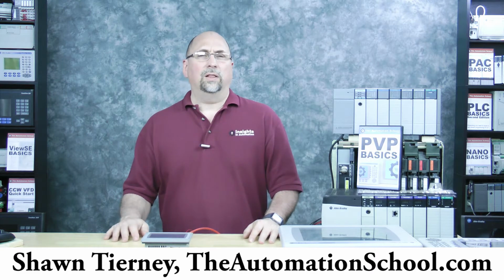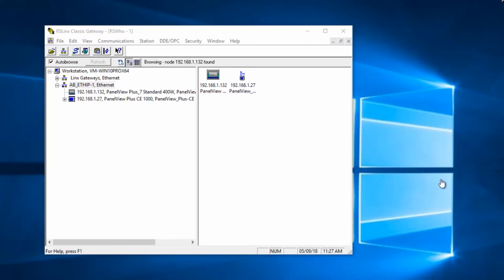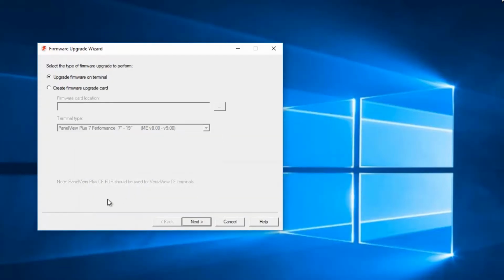flashing the firmware on the PanelView Plus 7. Here in RSLinx, you can see my PanelView Plus 7 is connected to the network with an address of 192.168.1.132. So my next step is to open the FactoryTalk View Machine Edition Firmware Upgrade Wizard. And that comes with View Studio. You can download it separately, but it's automatically installed when you install FactoryTalk View Studio.